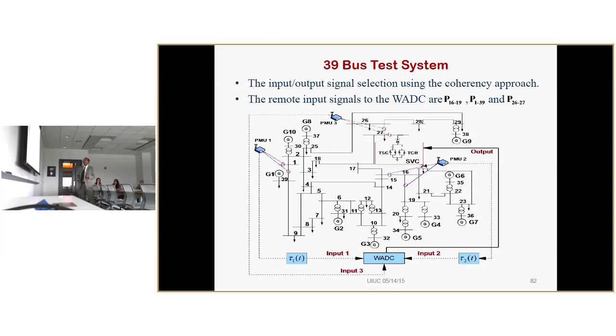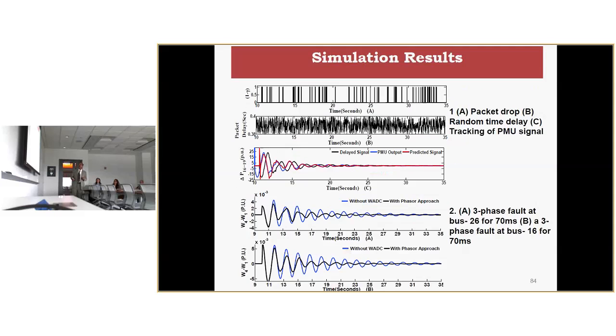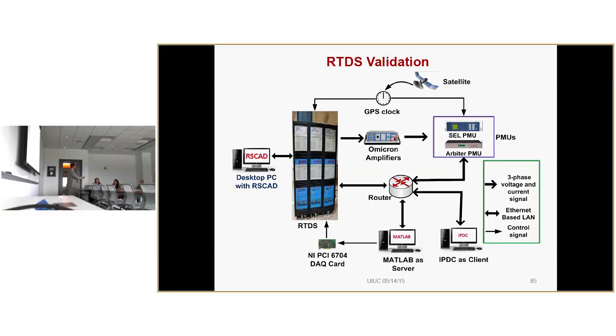Okay. And then we have tested it, again, on the 39-bus system. This is the diagram for the 39-bus system, where some FACTS controllers were also considered. And this is the random delay we applied. Packet drop also we simulated, random packet drop, random packet delay. And we verified whether it is matching with the current PMU output or not. So, closely matching. And then controller performance was verified. It gave the best result. And then finally, it was tested on RTDS.